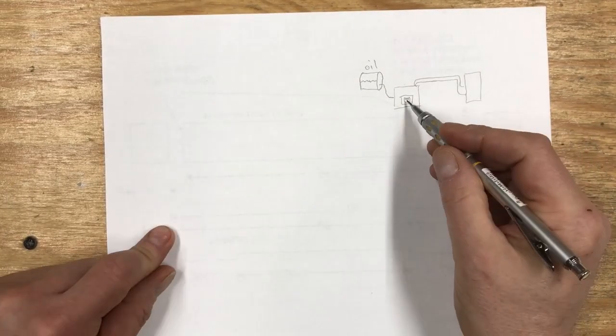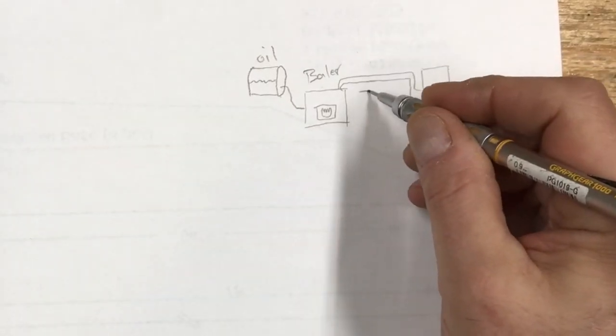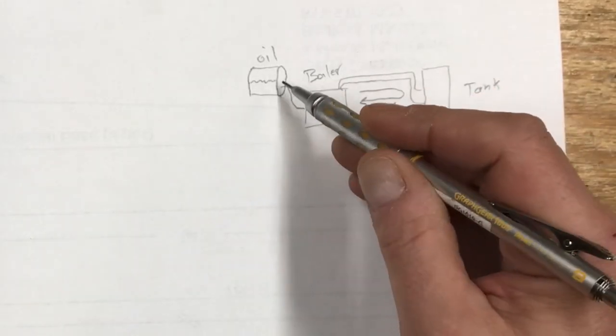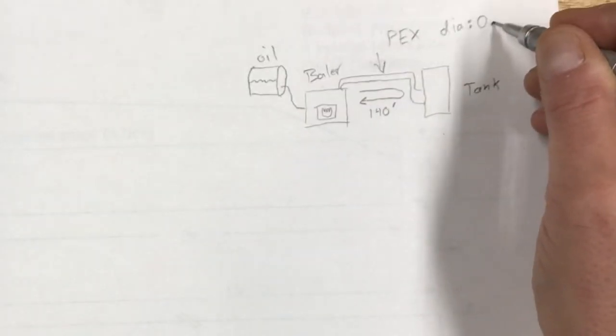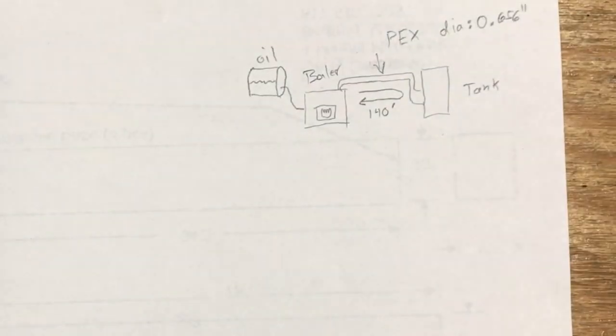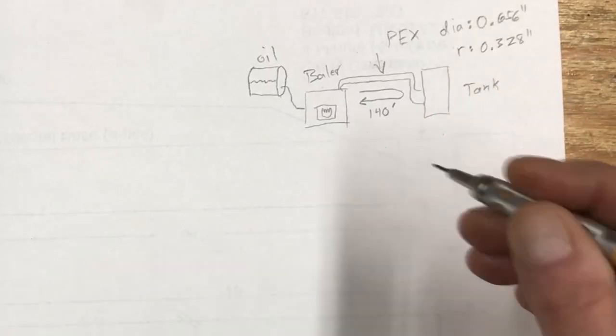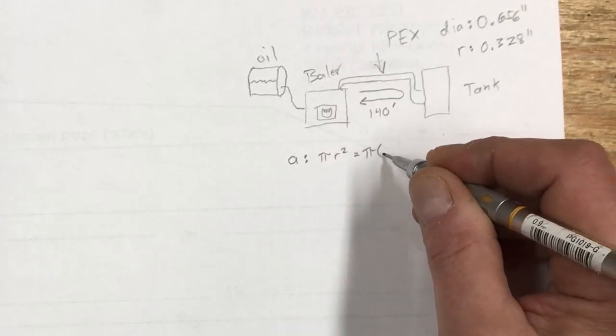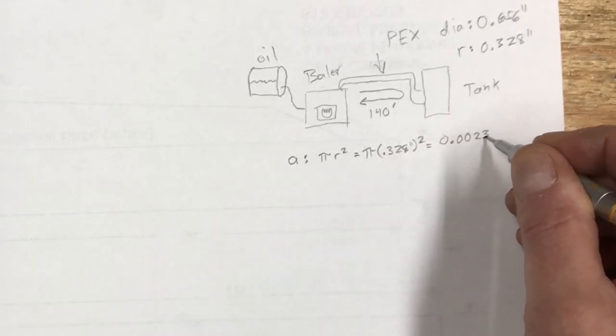Okay so I'm going to go to a pencil because it's a little finer. Here's my boiler and here's the tank. Earlier I said the round trip was 150 feet, it was actually a little bit less than that, I'm going to say it's 140 feet. The boiler is fired by oil so I have oil in a tank nearby to the boiler. This tubing here is PEX and as I said it has a diameter of approximately 0.656 inches so that means the radius is about 0.328 inches. So the area of the PEX is pi r squared is pi times 0.328 inches squared which if you do the math turns out to be 0.00235 square feet.